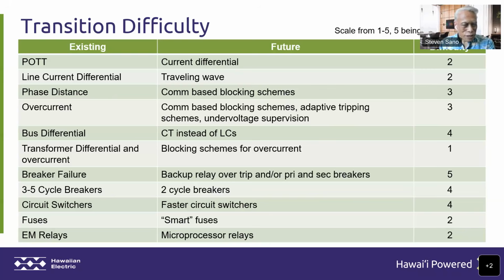Transformer current differential and overcurrent protection, blocking schemes for the overcurrent. Again, it's sort of localized to the transformer, so not that difficult. It's down at a 1 there. Breaker failure. Foregoing breaker failure, putting in a secondary breaker, that's a 5. That's going to be the most difficult thing for us, primarily because of space restrictions in our substations. We just don't have space for another breaker.